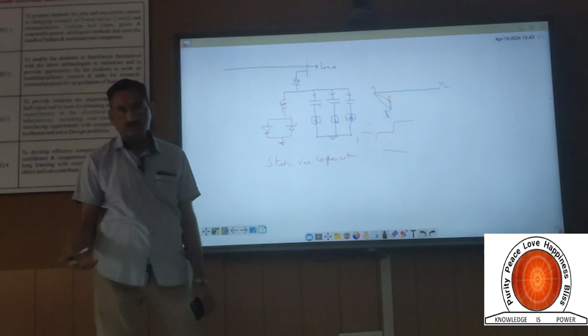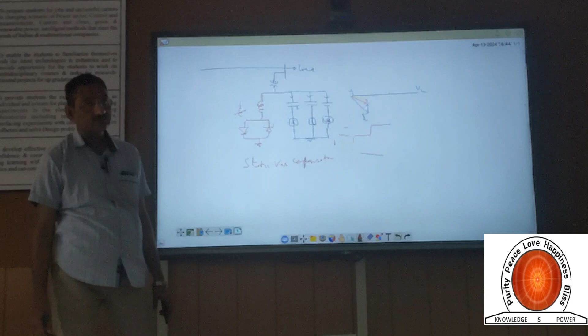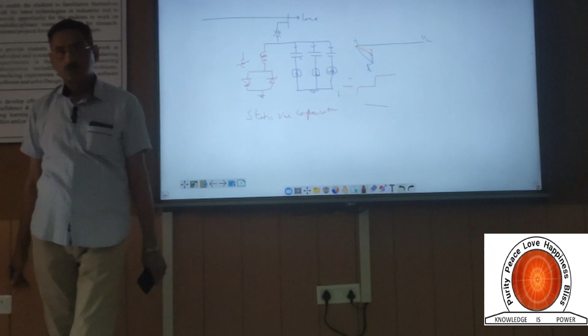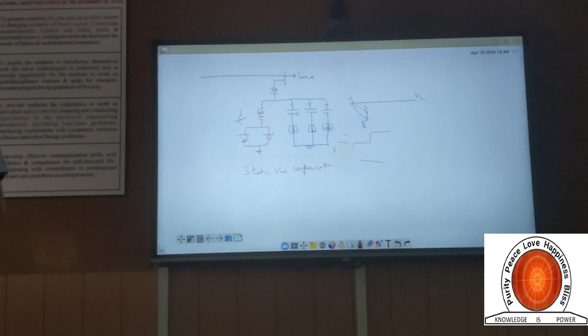Net current is changing, and depending upon the firing angle of this, the value of inductance can be changed. This value of inductance can be anything from one value to another value. So it is a variable inductance, so net reactance changes. So continuous control of the reactive power is done to maintain the continuous control of the voltage. To maintain a continuous voltage control, we need a continuous change of the reactive power.